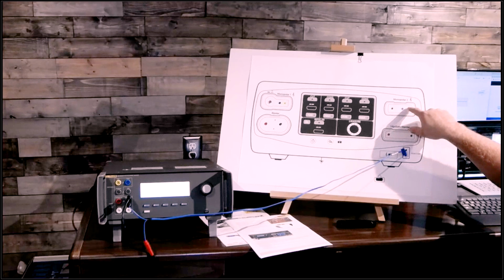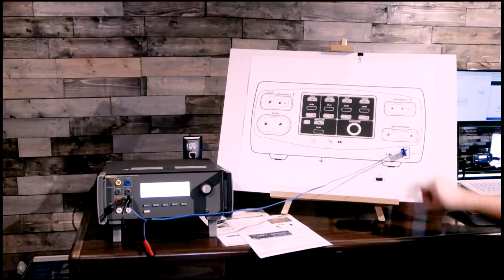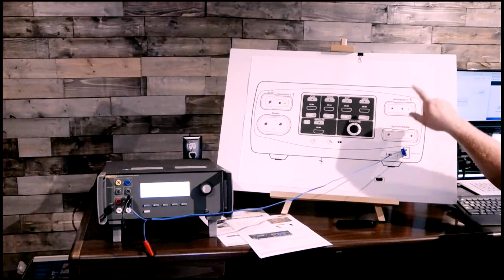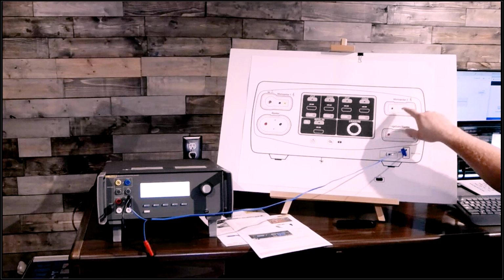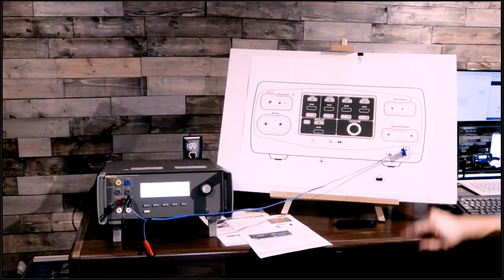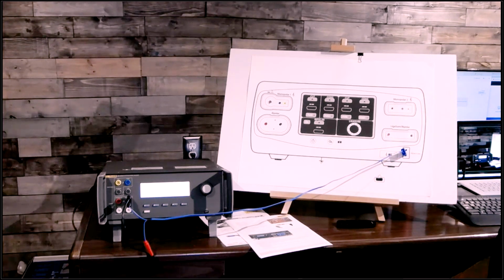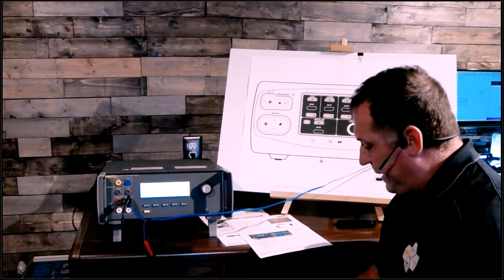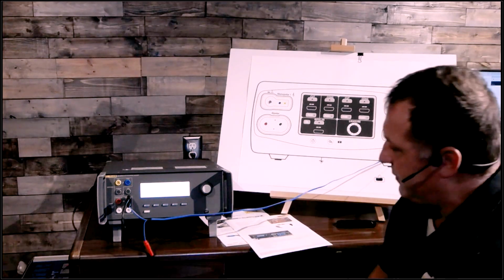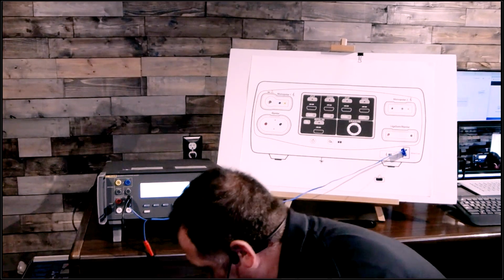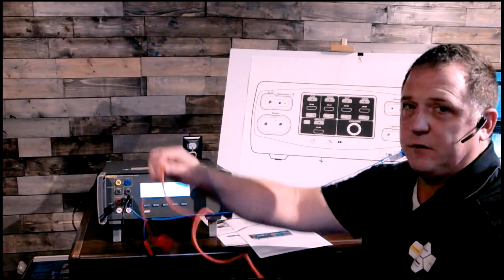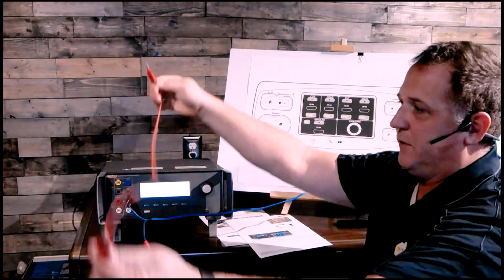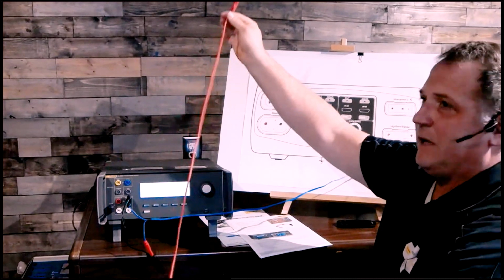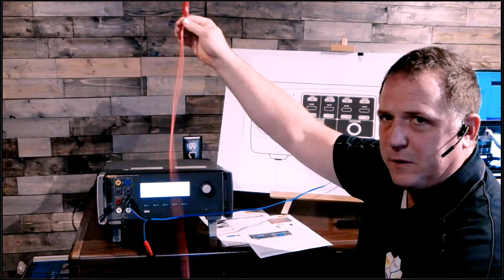So if you activate yellow, it trips this to this and turns on cut. If you do coag, you push the blue button, and it'll trip this and connect it to red, and your coag will turn on. So if I have the foot pedal in my ESU, the only thing I need to do then is take one of my red cables, and I like to use these ones with the piggyback. This is great for this. And I'm going to mention something. These are a specific length for a reason.